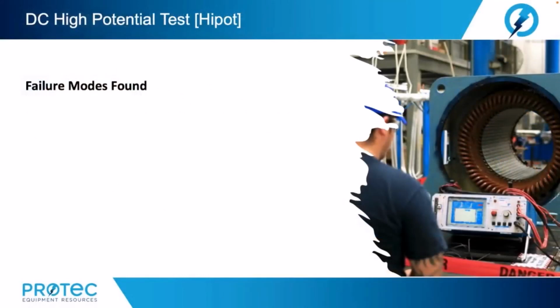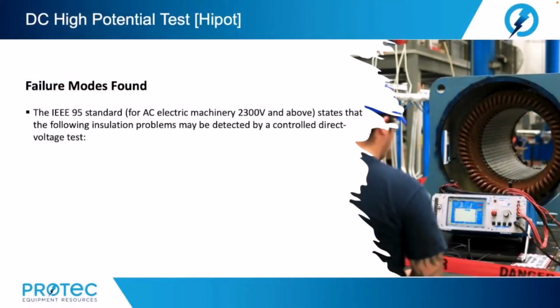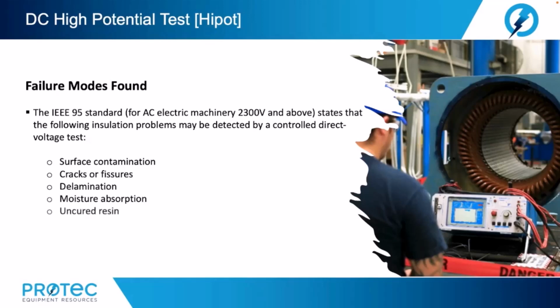Okay, other failure modes. The IEEE standard for AC electric machinery, 2300 volts and above, states that the following insulation problems may be detected by a controlled direct voltage test: surface contamination, cracks and fissures, delamination, moisture absorption, uncured resin, voids.